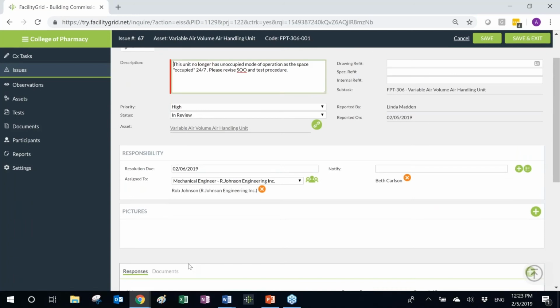And basically, again, what we've achieved was a few things. Number one is the controls contractor is aware of the type of testing procedure that's going to be performed during the functional testing with the commissioning agent. Number two is the functional performance testing procedure is now aligned with the sequence of operation that has been submitted as part of the control submittal, and also it matches what has been programmed for this particular piece of equipment. So the goal is basically to avoid any potential issues that would be caused by any of these issues coming up during the actual functional performance testing procedures.